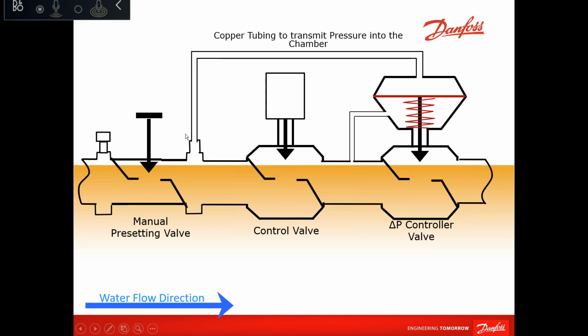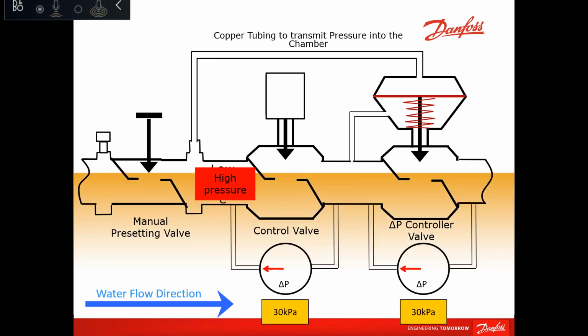In that case, you will have two openings or orifices inside the pressure control loop, and that would cause the authority of this control part of the PICV to drop if the effect of the setting mechanism is high. So now, in normal operation, nothing would happen. If we have a part load condition, somewhere else a valve will close, pressure will increase, and your modulating valve is closing. In that case, the pressure will be sensed, and the DPCV part of the PICV will close immediately.